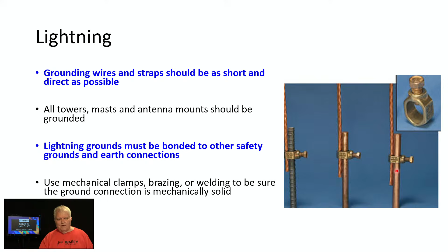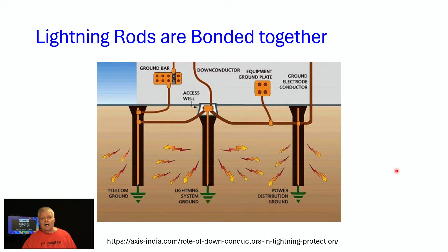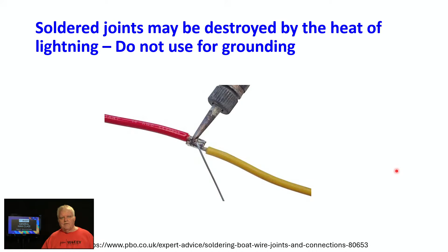And when you're connecting ground wires together, use mechanical clamps, brazing, or welding. There's something called CAD weld, we'll talk about in a second, that can join the wires solidly together, not solder. So you want lightning rods to be bonded together. Mechanical clamps are just fine. But if you're thinking about using solder like we use for electrical and electronic applications, solder joints can be destroyed by the heat of a lightning strike. And poof, they're open, and you've got no protection at all. So that's why solder is not used.